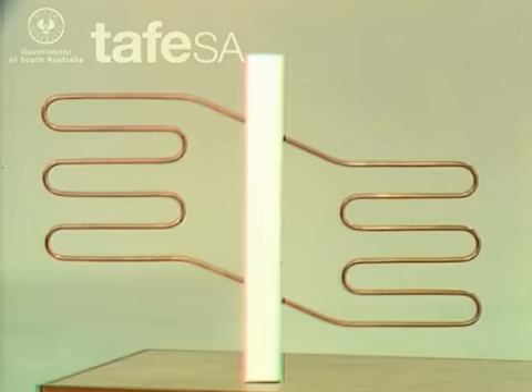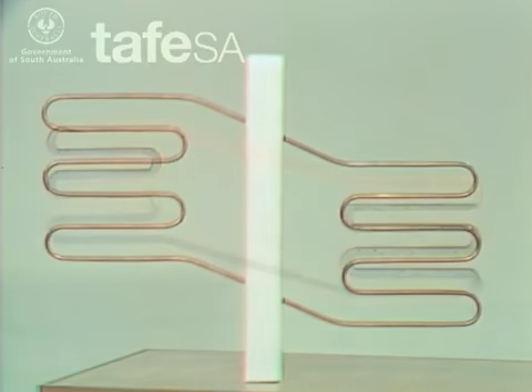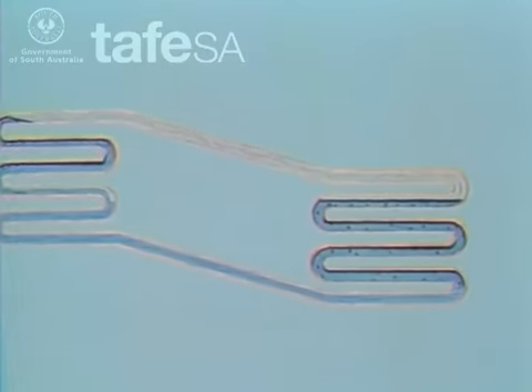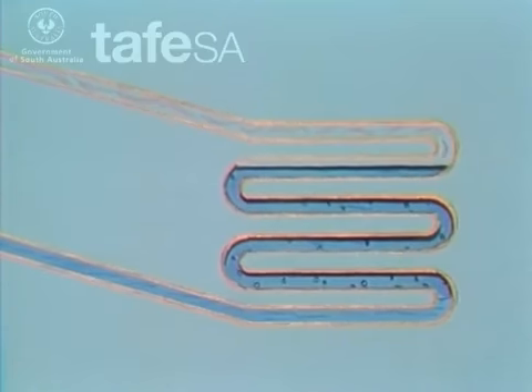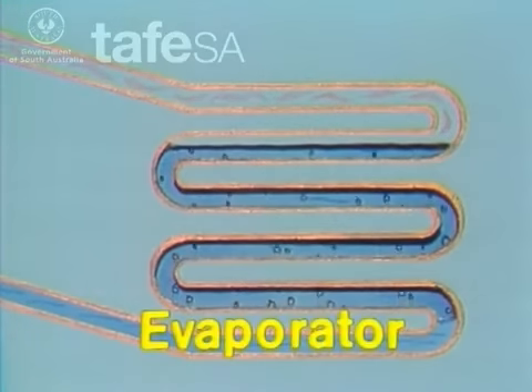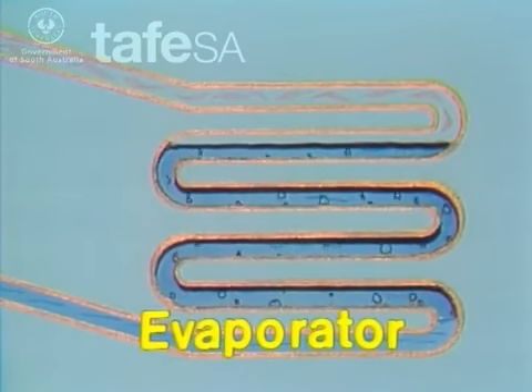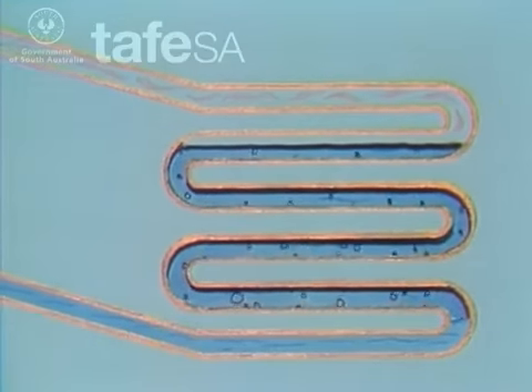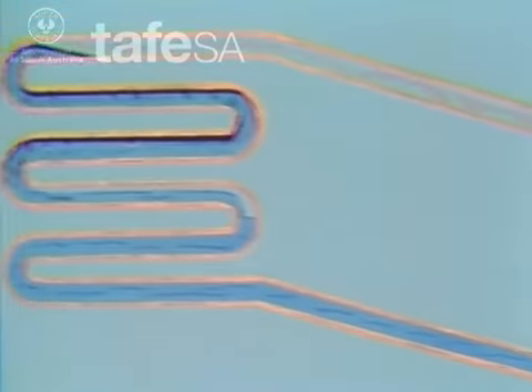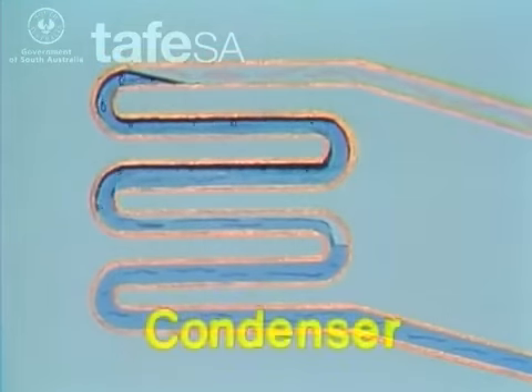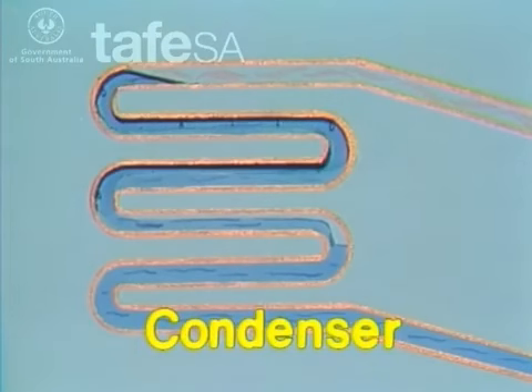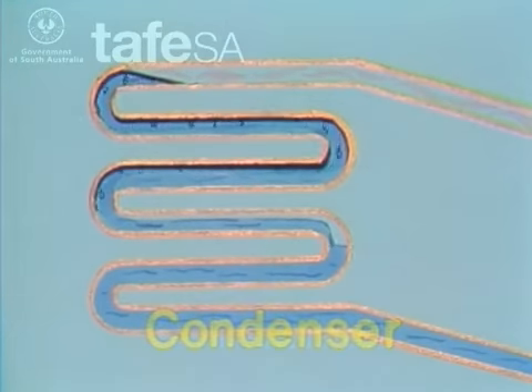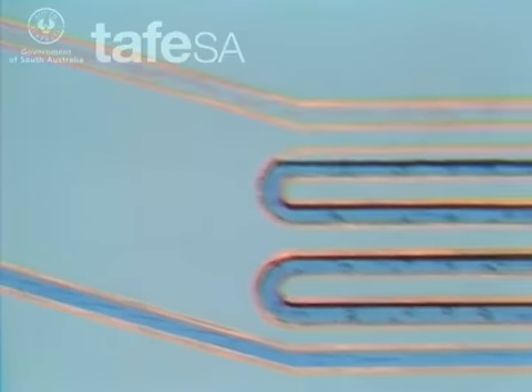If we were to imagine a situation where we wanted to transfer heat from a hot space to a cold space, then a simple closed system like this would do the trick. Refrigerant absorbs latent heat and boils in the heat exchange unit called an evaporator. The vapor travels to the other coil, the condenser, and gives up latent heat as it condenses. The liquid then returns to the first coil and the cycle continues.